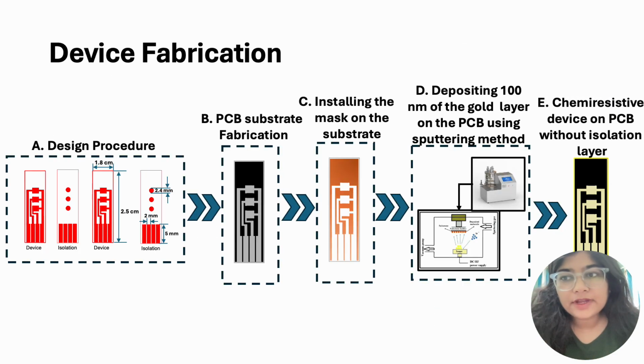To develop point of care diagnostic biochip, we first need to fabricate the device. The entire workflow of the device is as shown in this slide. We fabricate a three sensor array as shown, which has interdigitated microelectrode of 30 micrometer interfinger gap and 50 pairs of IDE each. So that's why our sensor has the capability of detecting three analytes of interest at a time for a particular disease.